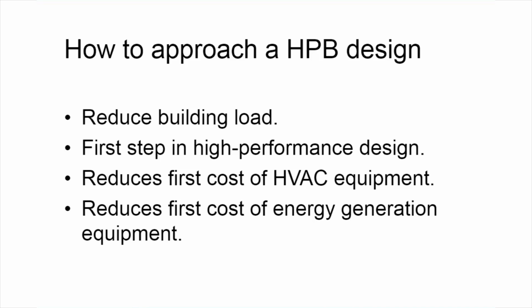So the first thing that you want to do is try to reduce all of those loads, optimize the HVAC equipment, use energy models to optimize the envelope and its effect on the sizing of that HVAC equipment, along with the lighting systems and what you can pull together there. The optimization and reduction of those loads is going to lead to reduced first costs of both the HVAC equipment and any energy generation equipment.